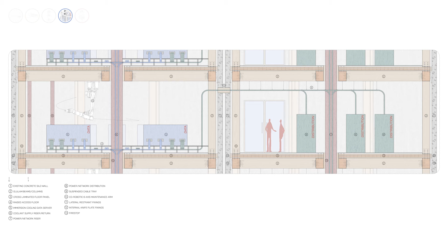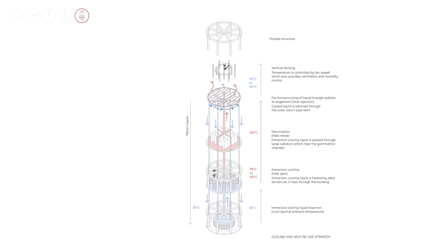The cooling strategy utilizes an electrically non-conductive liquid for the immersive cooling of data center equipment. This is pumped through the building, bringing the liquid heated by the data center servers to the germination module. Here, the heat is reused to maintain a constant temperature of around 30 degrees to promote the success of seed germination. The heat is then rejected through the use of a cooling fan, which can also control the temperature of the farming module above. The cooled liquid is then returned to the initial tank for the process to repeat.